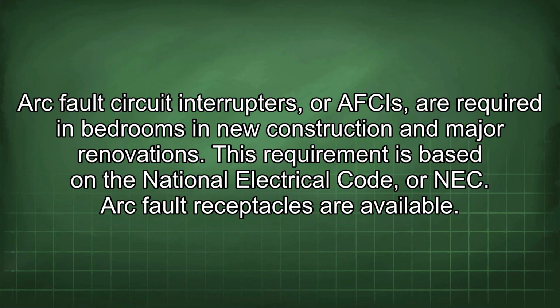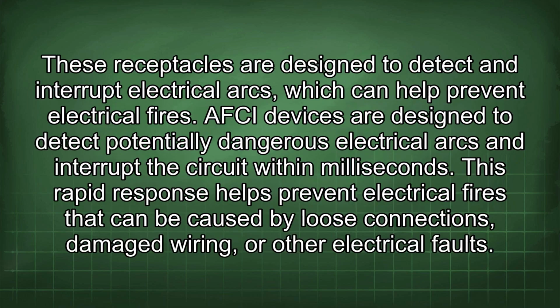Arc fault circuit interrupters, or AFCIs, are required in bedrooms in new construction and major renovations. This requirement is based on the National Electrical Code, or NEC. Arc fault receptacles are available. These receptacles are designed to detect and interrupt electrical arcs, which can help prevent electrical fires.